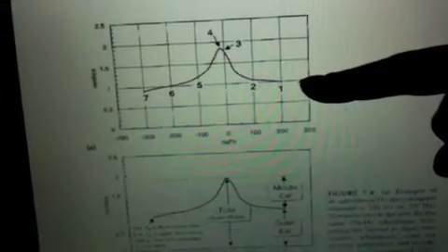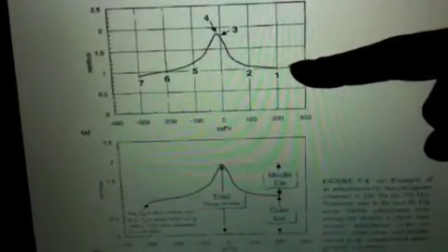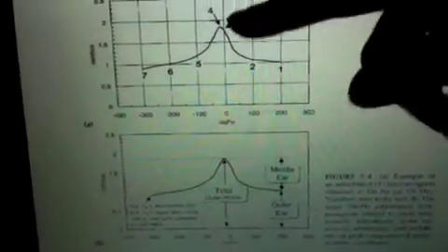When we have positive pressure being introduced into the external auditory canal, admittance, or the ease of energy flow in the system, is relatively low. As the pressure begins to change and become more consistent with atmospheric pressure, admittance into the system is increased. This is a key factor of tympanometry, and one that you should be sure you're comfortable with. As pressure on either side of the tympanic membrane is equal, you'll see the greatest admittance, or ease of energy flow into the system.